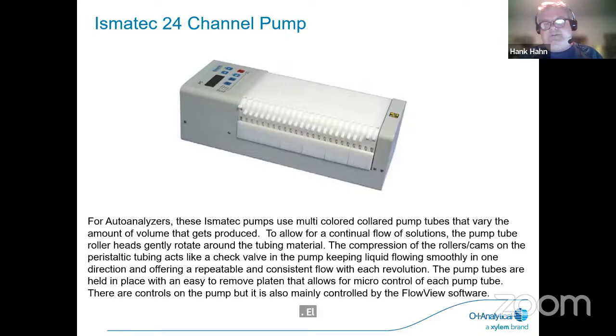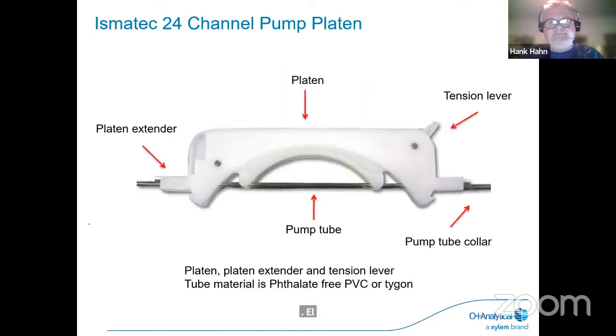And it goes on a principle of rollers, cams, the peristaltic tubing. It acts like a check valve in the pump, keeping the liquid flowing smoothly in one direction. It offers repeatable and consistent flow with each revolution. So here's the 24 channel pump with the platen and the platen extender. So this is an example of the platen. We have the pump tube that fits in, the pump tube collar that snaps into the platen extender, and you can change those out quite quickly.